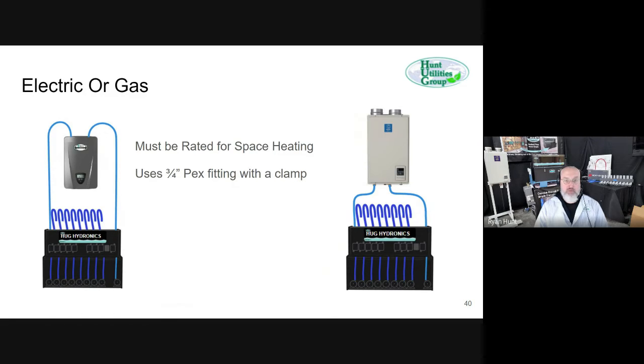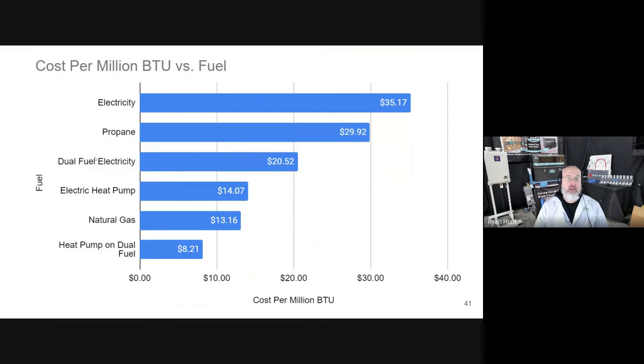Once you know the size, then it's the fuel: electric or gas. We have both options. And the fuel cost is definitely the most important thing. Electricity is usually the highest cost. Dual fuel electricity cuts that a lot. Propane and electricity are in the same ballpark. This is only a snapshot in time. Things change. Propane changes cost over the course of a year and from year to year. It varies with where you're at. And in some cases, electricity is pretty constant. It just slowly goes up over time, but it's not volatile the same way that natural gas and propane are. Natural gas has had a few spikes, but it's significantly cheaper than electricity and propane. If you can do a heat pump on dual fuel, that's definitely a win. That's the best that you can get.